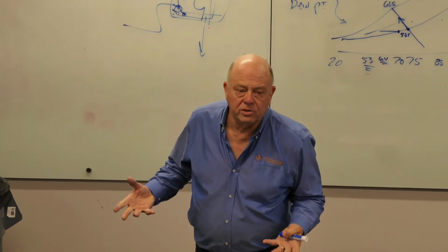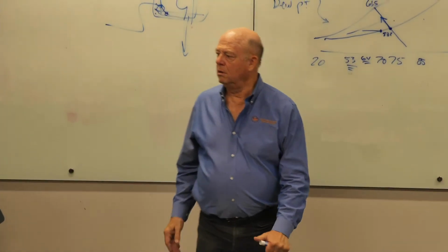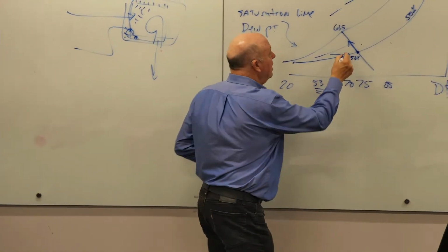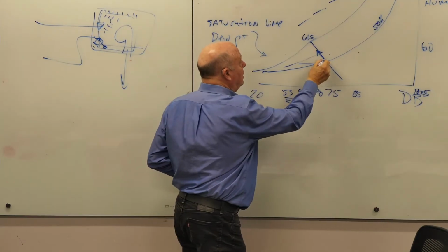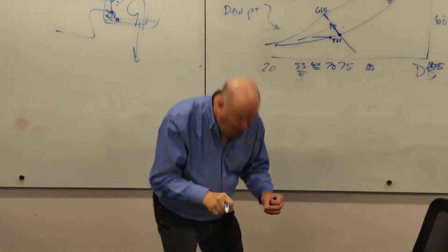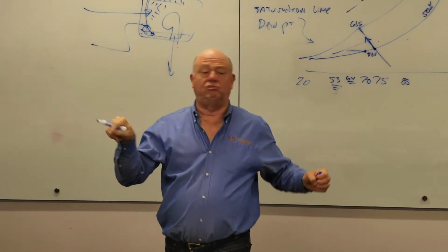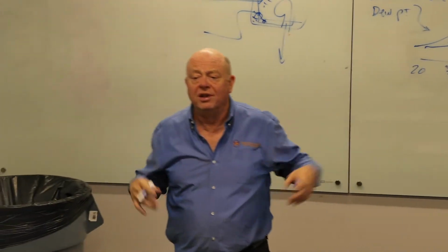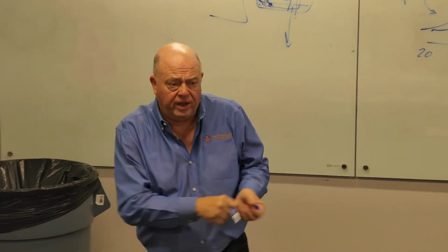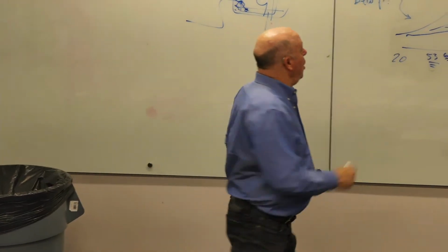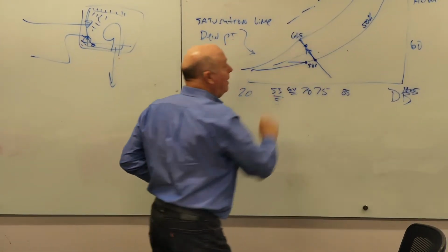In other words, you'll get 70 or 80% of the way to saturation. If you took your ruler and measured this line on the chart at 75% of the distance, and it was 75% efficient according to the catalog, you'd know that's the new spot.